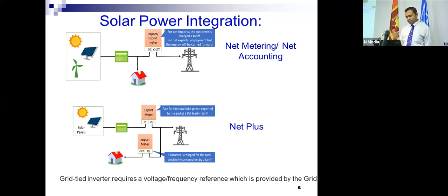In all these scenarios, we are using an inverter, what we call a grid-tied inverter. A grid-tied inverter requires voltage and frequency reference, which is provided by the grid. Without the grid, you cannot operate the inverter, because every inverter needs a reference for voltage and frequency, and that reference comes from the grid. If you can make that reference by yourself without the grid, then you can use your own electricity even without the grid.